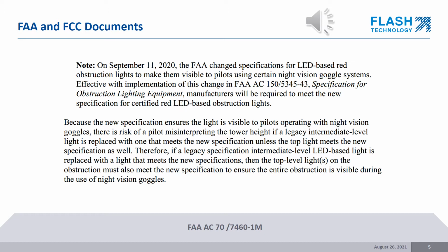On September 11, 2020, the FAA changed the specifications for LED-based red obstruction lights by integrating all LED lighting systems moving forward with IR. The fear is the misinterpretation of the overall tower height, which becomes potential when updated lighting systems or lights are mixed with legacy systems.